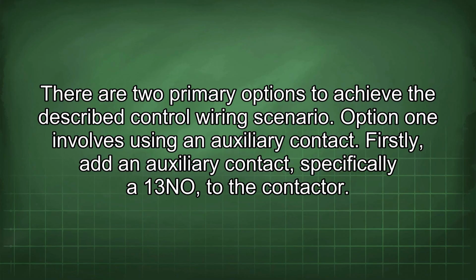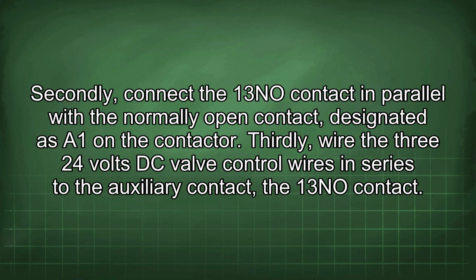There are two primary options to achieve the described control wiring scenario. Option 1 involves using an auxiliary contact. Firstly, add an auxiliary contact, specifically a 13-NO, to the contactor. Secondly, connect the 13-NO contact in parallel with the normally open contact designated as A1 on the contactor. Thirdly, wire the 24 volts DC valve control wires in series to the auxiliary contact, the 13-NO contact.